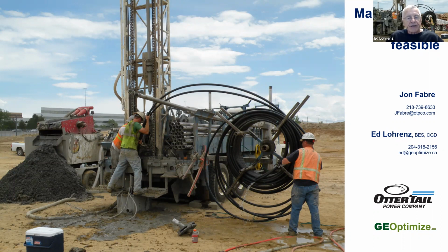You're touching more unaffected dirt with more of the boreholes if you've got a long skinny borehole field than if you've got a square or close to square borehole field. And that makes a big difference. You're basically touching more unaffected dirt with a different layout. And that's something that you can model very easily in some of the software. So it's certainly worth looking at.